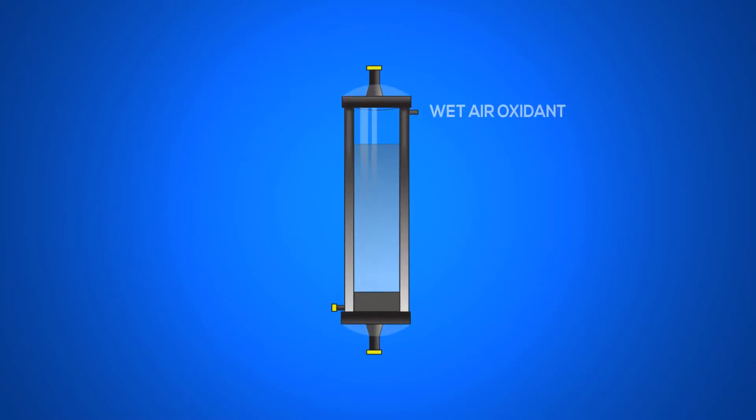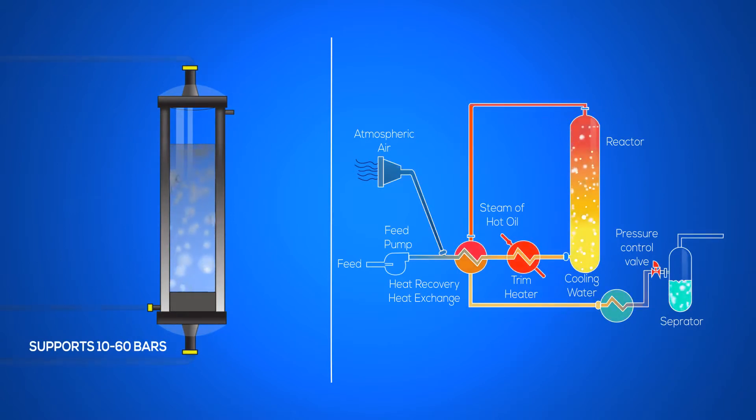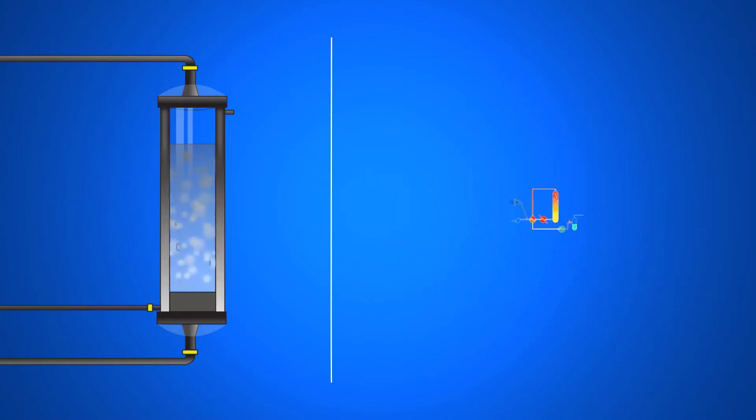Developed 60 years ago, wet air oxidation uses large bubble reactors that support low or medium pressure from 10 to 60 bar and uses air as oxidant to oxidize the contaminants within liquid waste streams. Retention time is often 90 minutes. These wet air oxidation systems were the first generation of wet oxidation.